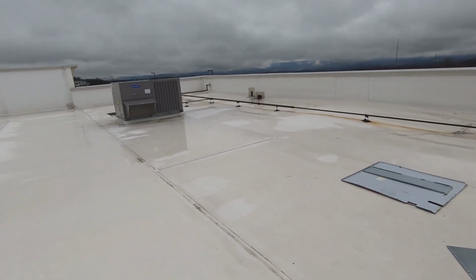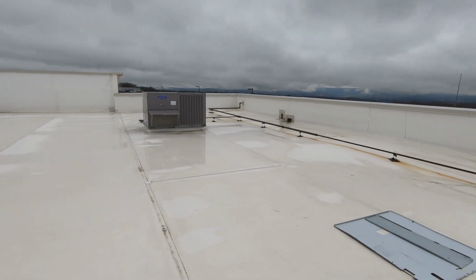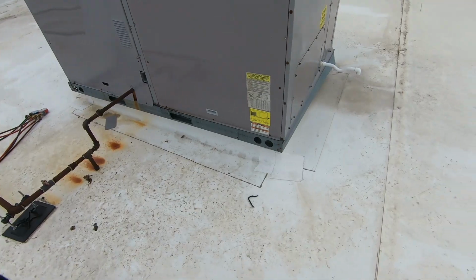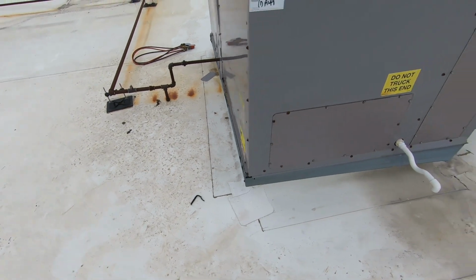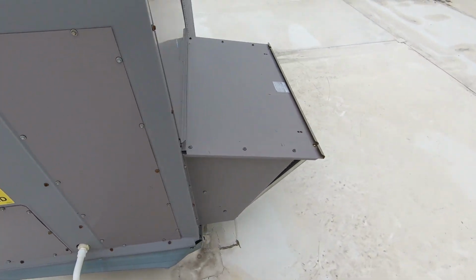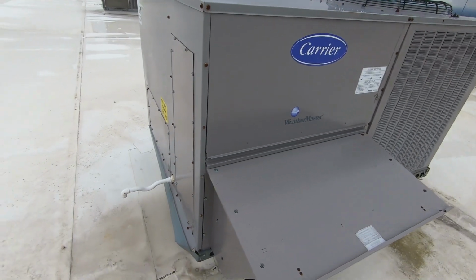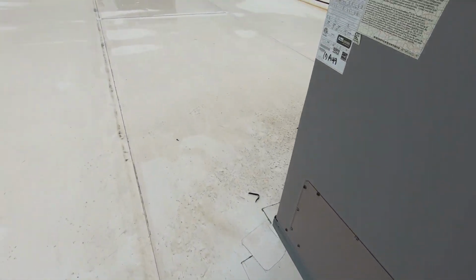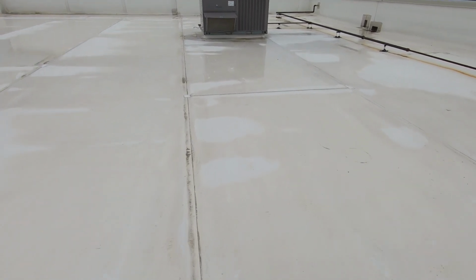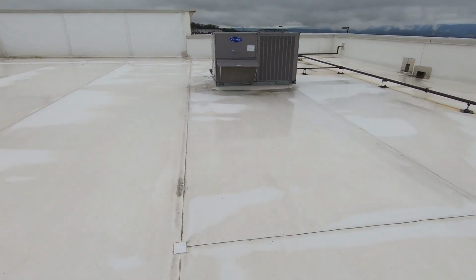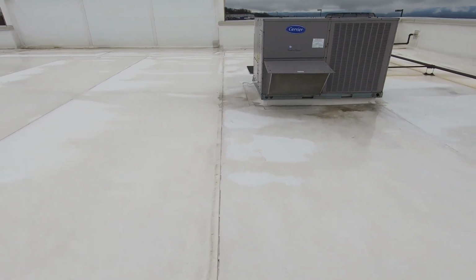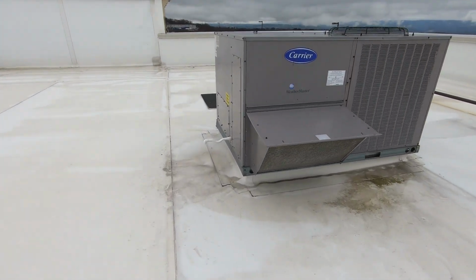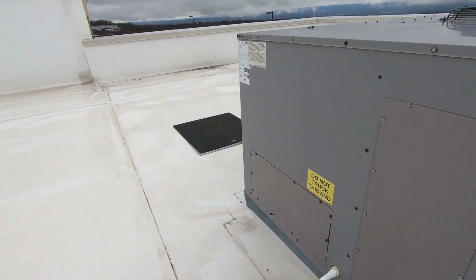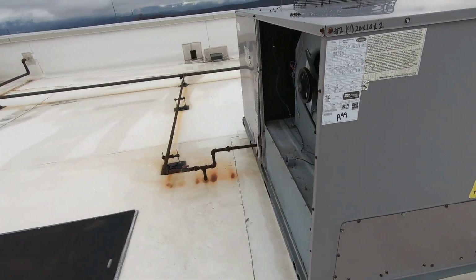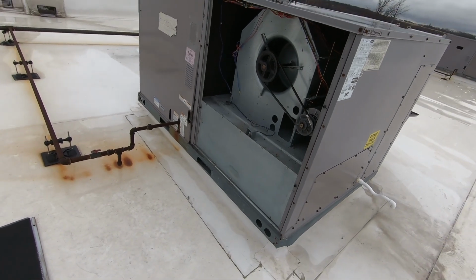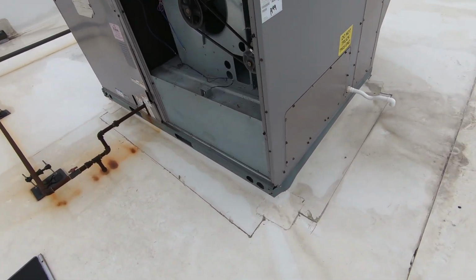I'm gonna go over there, cycle that one, check its heat exchanger, make sure it's good to go, and then we'll do the write-up. I disconnected the low volt wires, shut the gas off, and left the disconnect off until we can come back and replace the blower motor, install the proper limits, safety switches for it to operate properly, and give that wiring a full investigation and inspection, replace anything that needs it, make sure everything is working properly and good to go. What are the chances this heat exchanger's cracked?